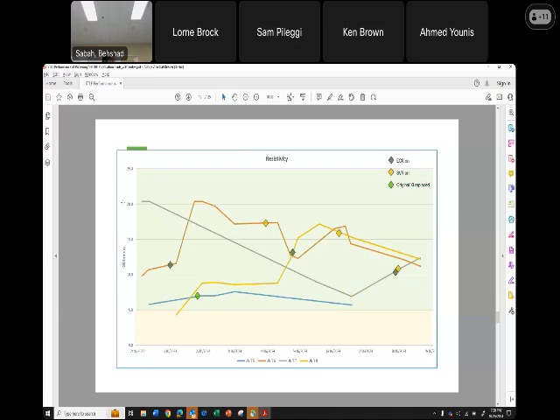Next. So resistivity, like I said, when we first started using the other brand of resin back in 2013, we saw resistivity drop below one, basically, which is not good. But in this case, we see resistivity increase, especially when we turn the electrostatic separation on, which are the gray triangles, the ECR. When we turn those on, we see a very dramatic increase in resistivity. And for some reason, not so much when we turn the resin on, which is the SVR. And then if you look at unit five, the resin basically does nothing. The resistivity stays fairly low.